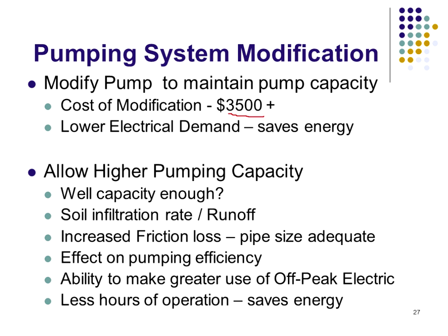By doing this, we're going to lower the horsepower requirement of the pump, which will save energy in that regard. The other possibility is to allow the pump capacity to increase or go higher. We have to make sure that the well has enough capacity. So we need to do a test on the well to make sure it can supply enough water without cavitation. If it does cause cavitation, we may need to lower the pump in the well. But that's the first thing.